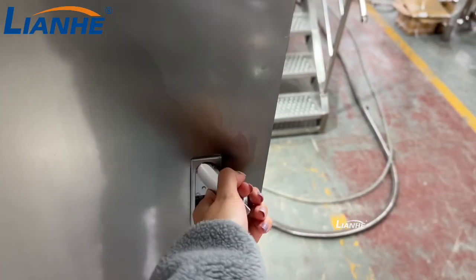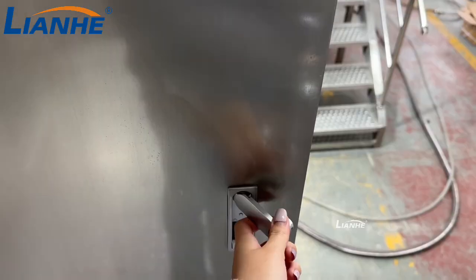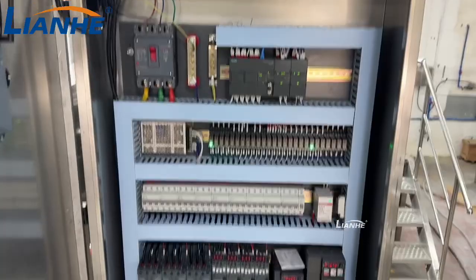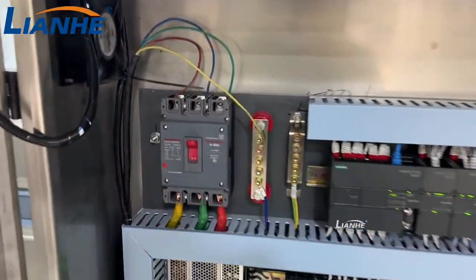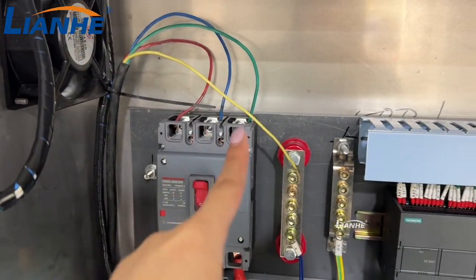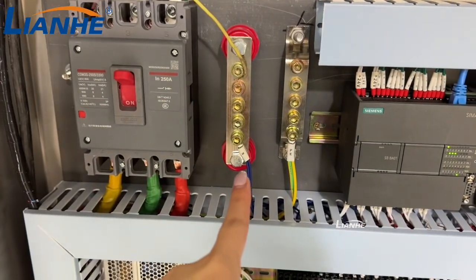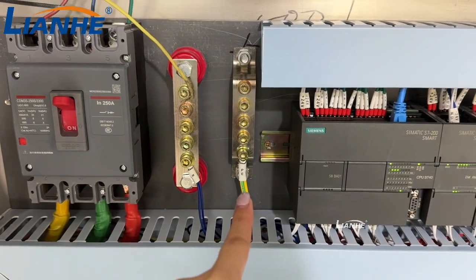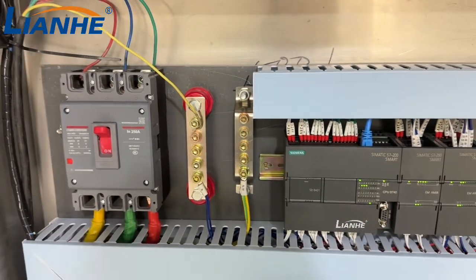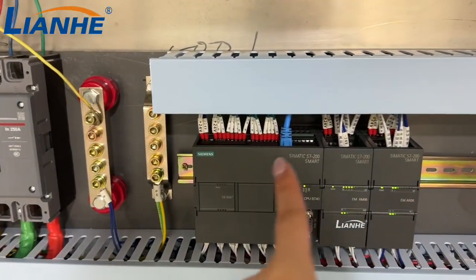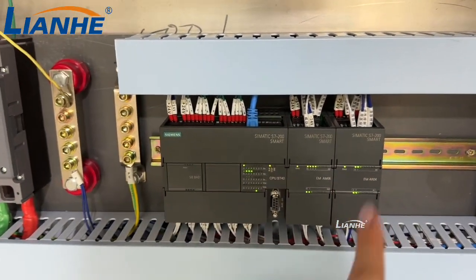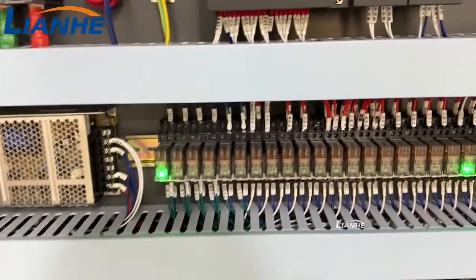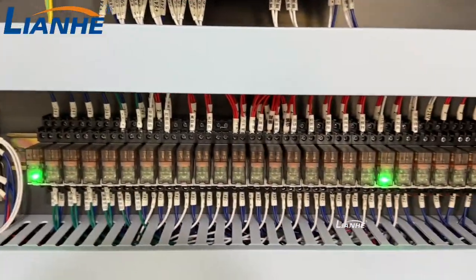And you can open this cabinet. And then you may check inside. Here are the L1, L2, L3 wire. This one is the neutral wire and the ground wire here. You should connect these 5 wires. And then you can see here are the other wires. We also mark the number on it.